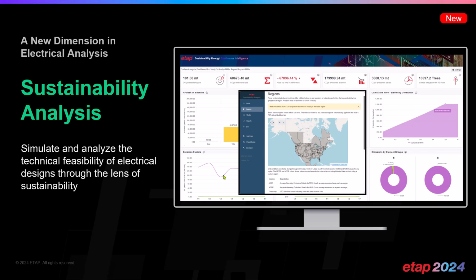The current dimensions that exist include technical losses, so we have a technical dimension to compare design A versus design B. We have another dimension, reliability, such as failure rates, again used to compare the effectiveness of design A versus design B. We have economics, also used to measure the effectiveness of the design. We have stability or resiliency, using analysis like transient stability or voltage stability to understand how resilient or stable a design is under various conditions. And now we have sustainability, which lets us use the lens of carbon footprint and carbon emissions to understand the sensitivity and capability of the design as yet another dimension.